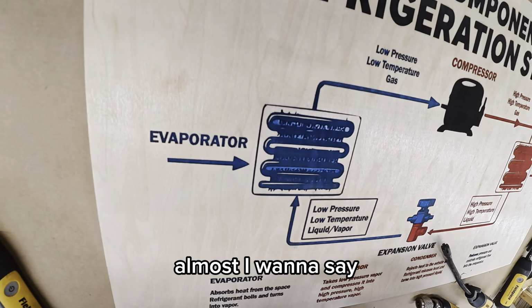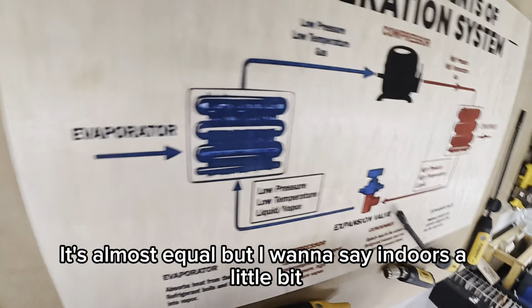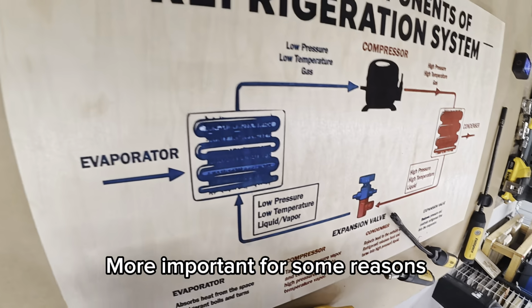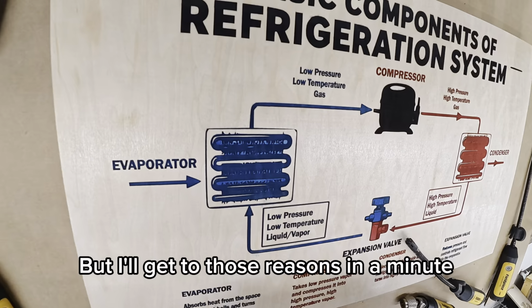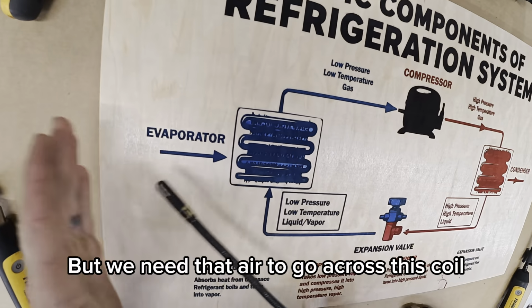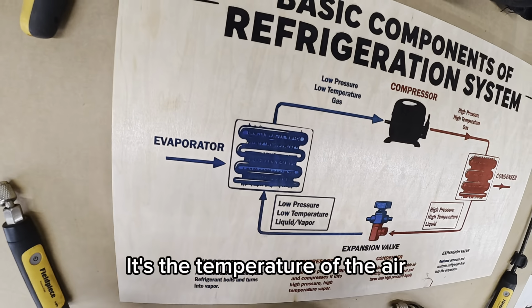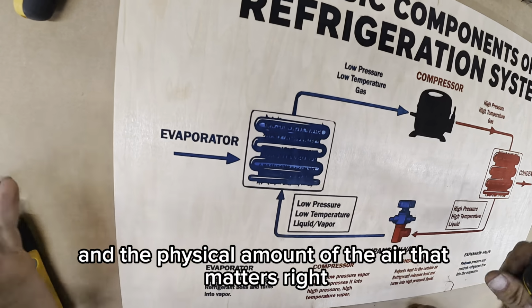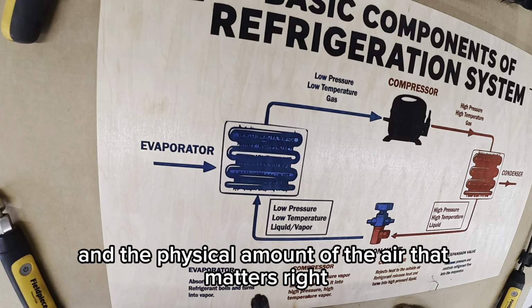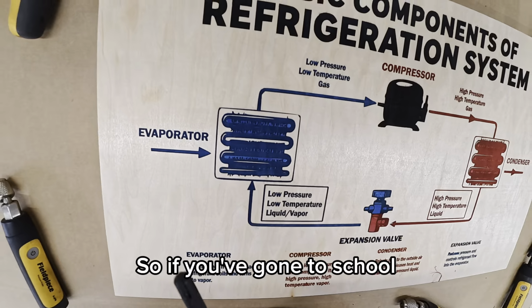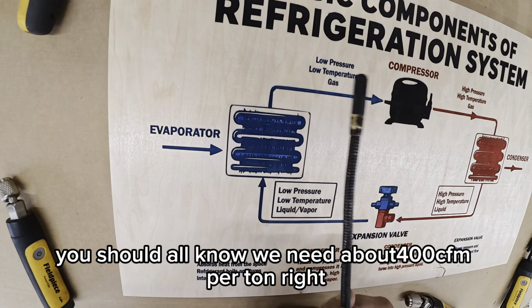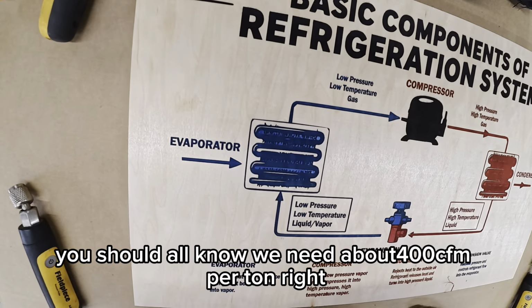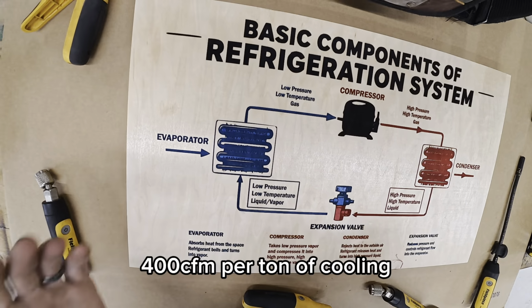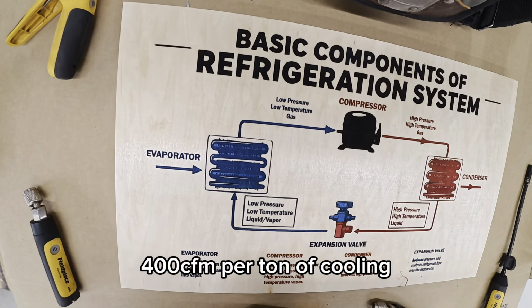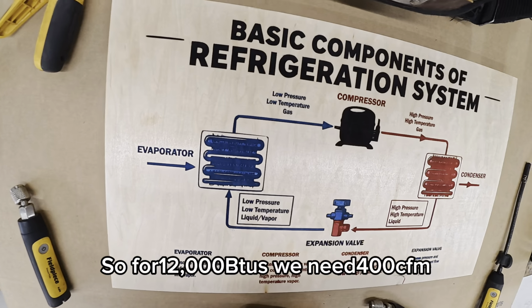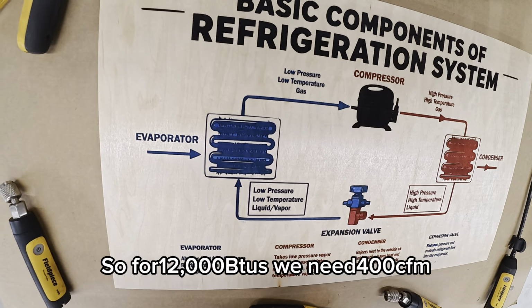Almost, I want to say it's almost equal, but I want to say indoor is a little bit more important for some reasons, but I'll get to those reasons in a minute. But we need that air to go across this coil. It's the temperature of the air and the physical amount of the air that matters, right? So if you've gone to school, if you're in the trade a little bit, you should all know we need about 400 CFM per ton, right? 400 CFM per ton of cooling. So for 12,000 BTU, we need 400 CFM.